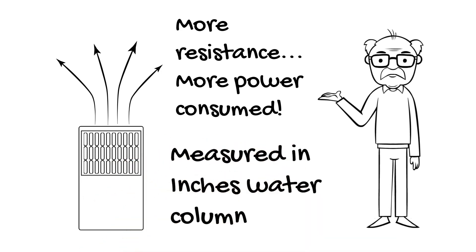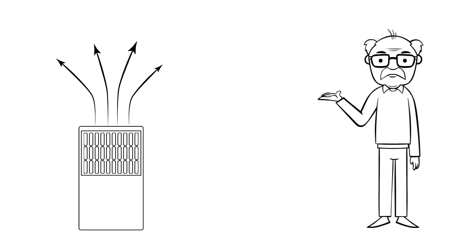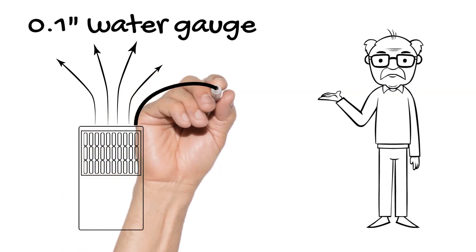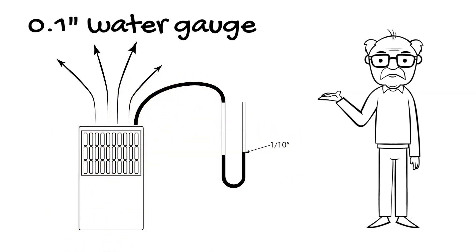This resistance is measured in inches water column. That is, the amount of pressure it takes to push a column of water up a tube. In the past, the test was made at 0.1 inches water column. That's not a lot of pressure, only one-tenth of an inch.